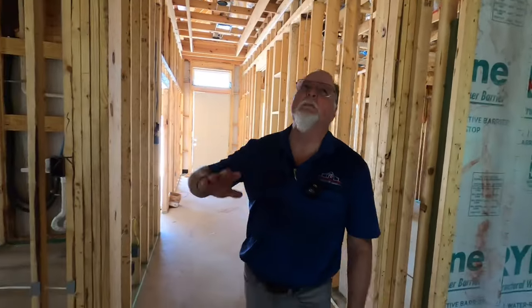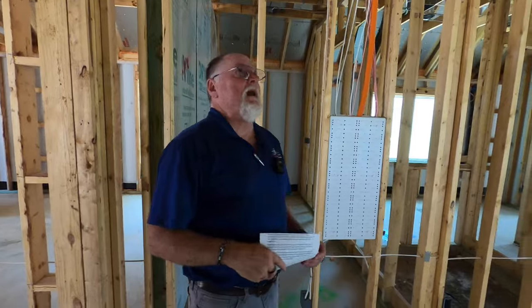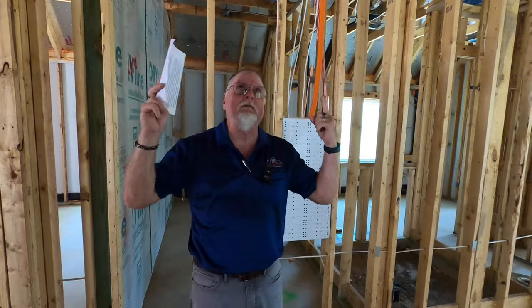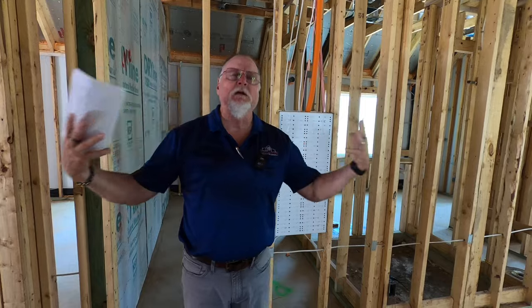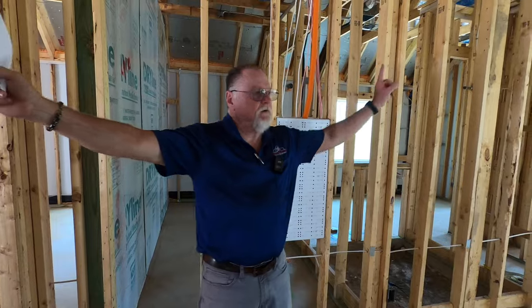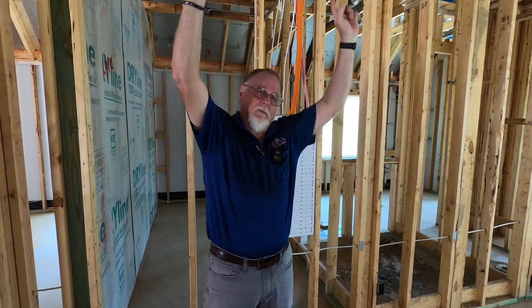The things that kill foundations is either too much water or not enough. This is not going to be a foam-blown home, but if you are getting a home that is foam blown, that is a sealed, unvented attic. The problem with a sealed, unvented attic is you typically have an air conditioner up there producing condensation in an unvented space. What a lot of good builders are doing is putting a supply register and a return register to actually circulate air through that unvented attic, so the air temperature there is virtually the same as the interior of your home. That is highly advisable.